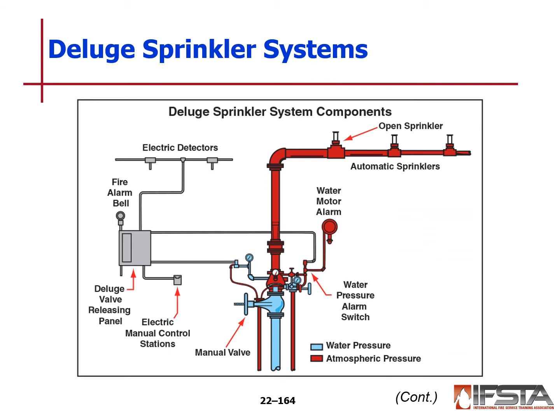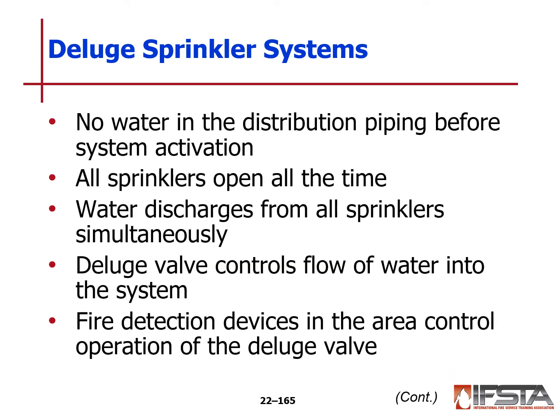Your deluge systems and their components: all of the heads in these are open, and so there will be a water pressure switch. You'll have a deluge valve. This can also be manually operated, and you may have electronic detectors that are tied into your valves. So when it either detects or is manually triggered, it will then charge the system and all heads will flow at the same time. In this type of system, because all of the heads are open, there's no water in the distribution piping before the system is activated. All sprinklers open all at the same time. Again, water discharges from all the sprinklers simultaneously.